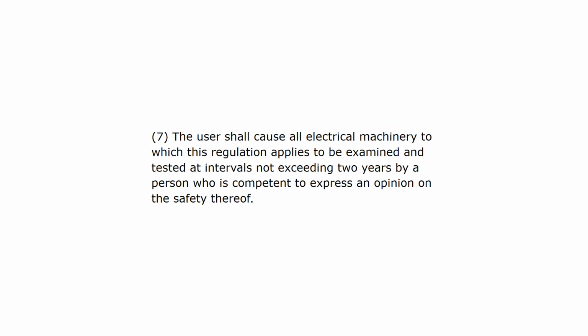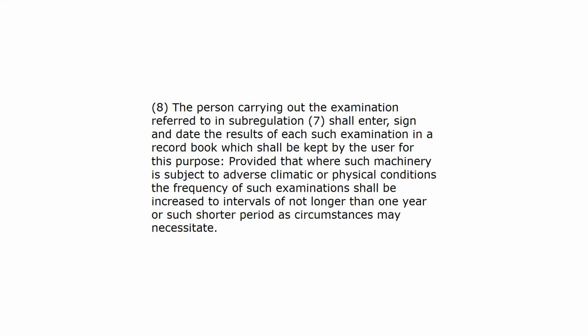The user shall cause all electrical machinery to which this regulation applies to be examined and tested at intervals not exceeding 2 years by a person who is competent to express an opinion on the safety thereof. The person carrying out the examination referred to in sub-regulation 7 shall enter, sign, and date the results of each such examination in a record book, which shall be kept by the user for this purpose, provided that where such machinery is subject to adverse climatic or physical conditions, the frequency of such examinations shall be increased to intervals of not longer than 1 year or such shorter period as circumstances may necessitate.